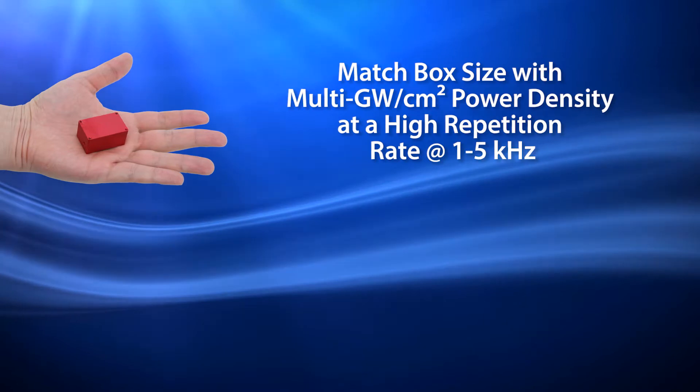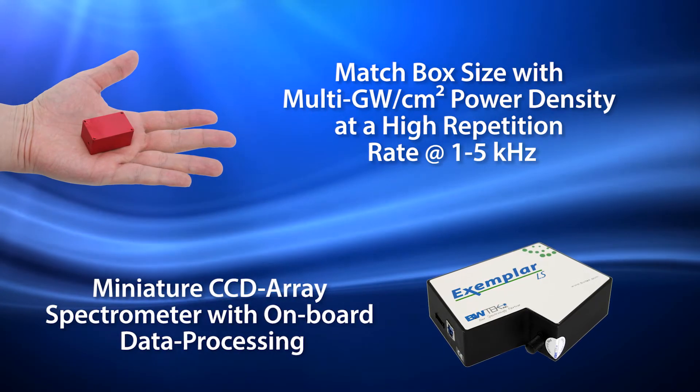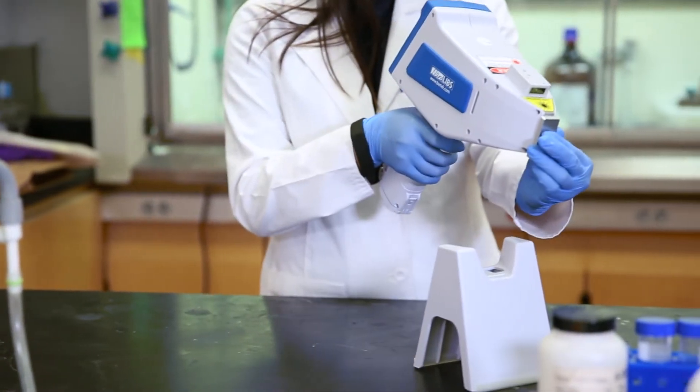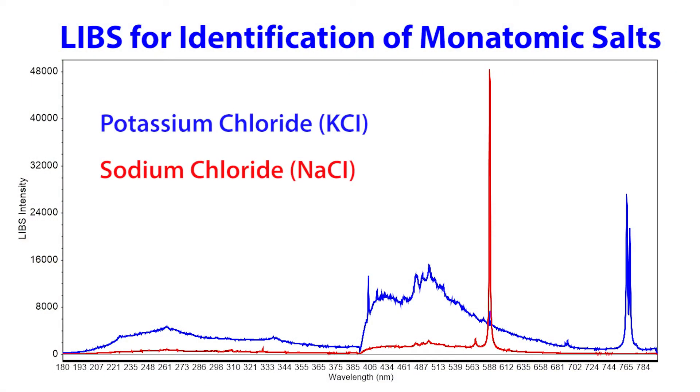The NanoLibs uses B&W Tek's patented high-repetition rate laser and miniature spectrometers to deliver a highly integrated handheld solution. The minimally destructive LIBS technology of the NanoLibs is ideal for identifying monatomic salts, such as potassium chloride and sodium chloride — key raw materials for most injectable and infusion pharmaceutical products.